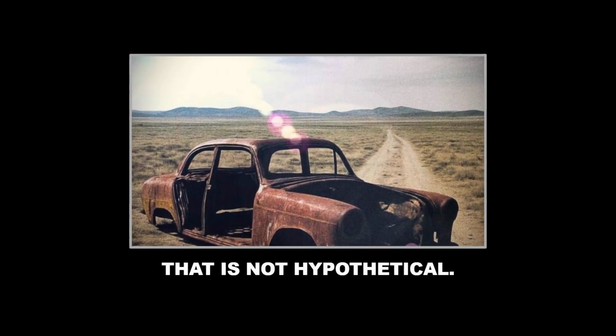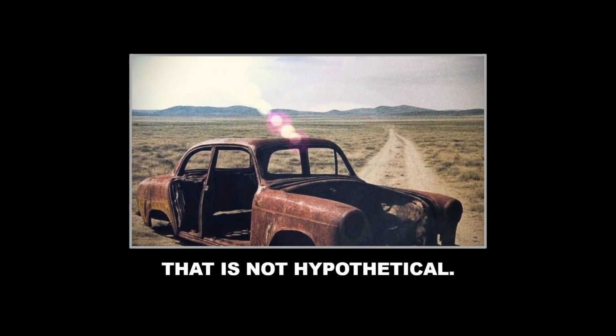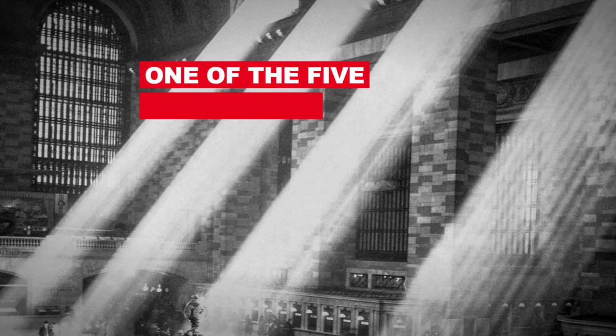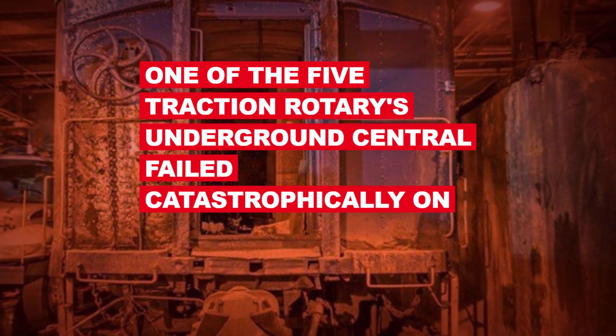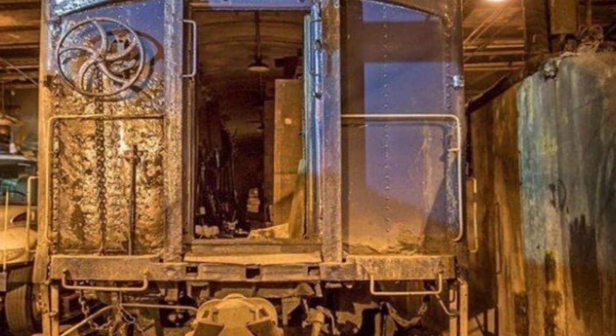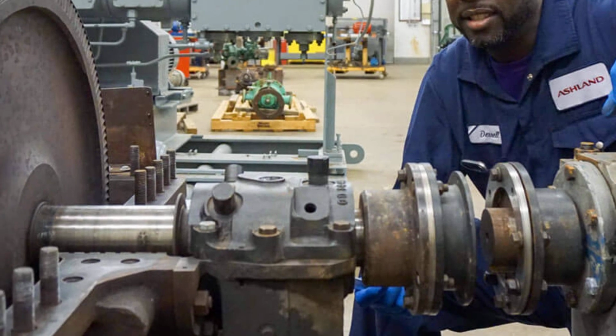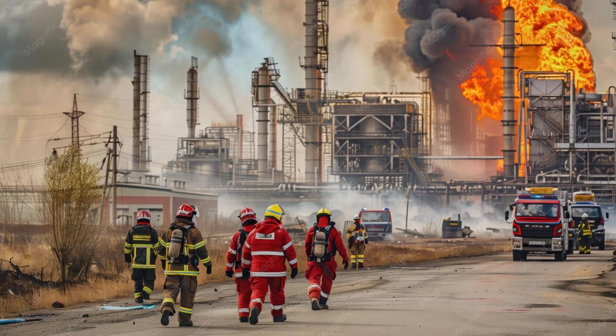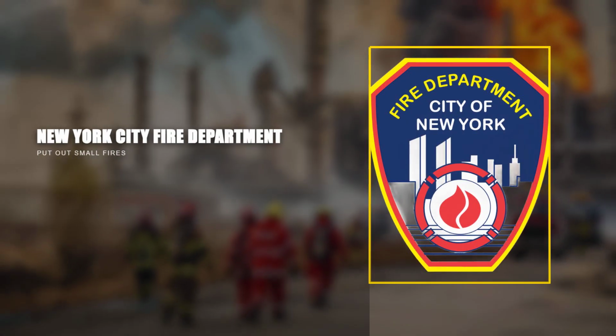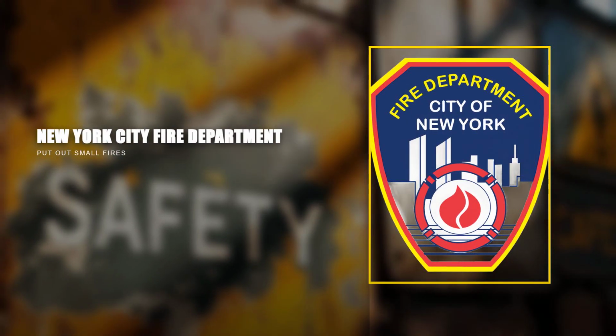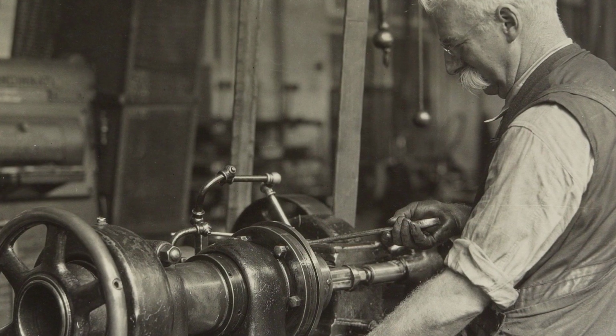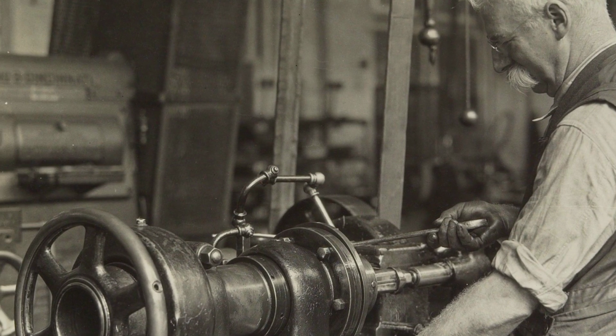That is not hypothetical. In March 1988, one of the five traction rotaries under Grand Central failed catastrophically on its own. It threw hot metallic shrapnel across the substation and started small fires that the New York City Fire Department had to put out. Nobody was hurt. Nobody sabotaged that machine. By that point, only two or three of the five had been operational for years, which meant the survivors were being overloaded through every morning and evening peak.